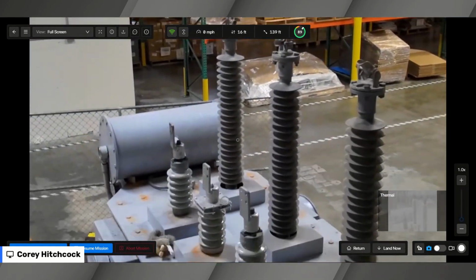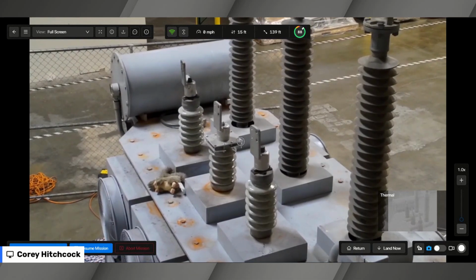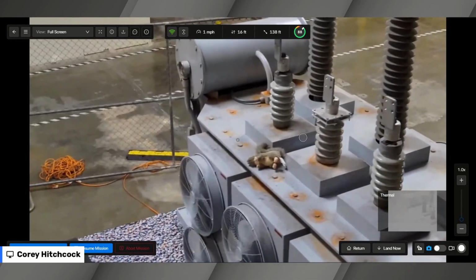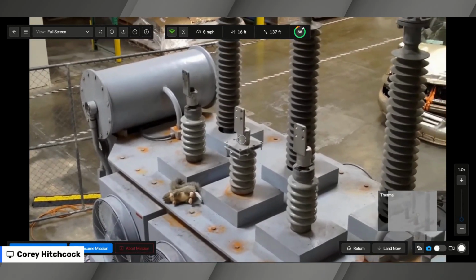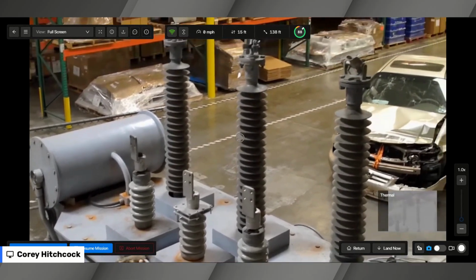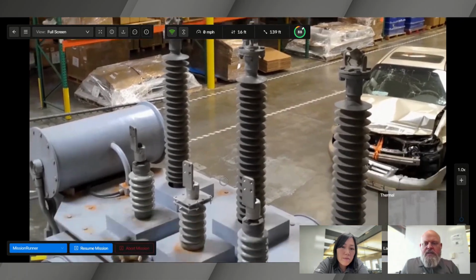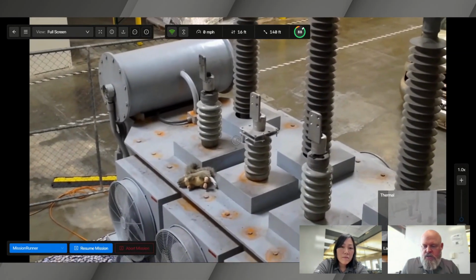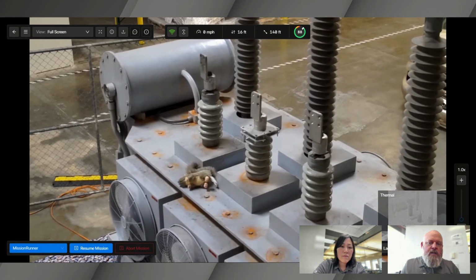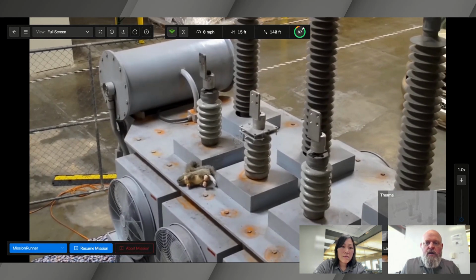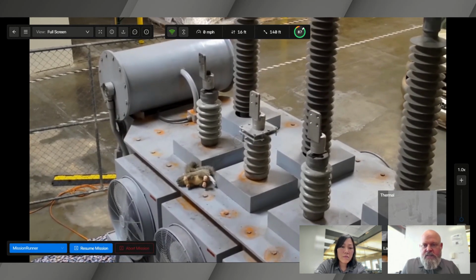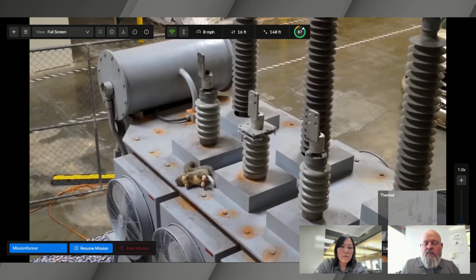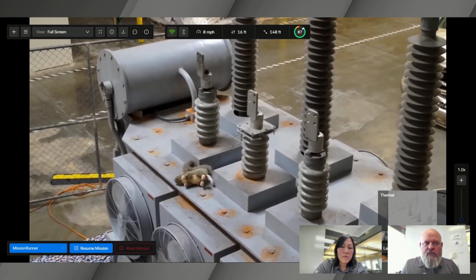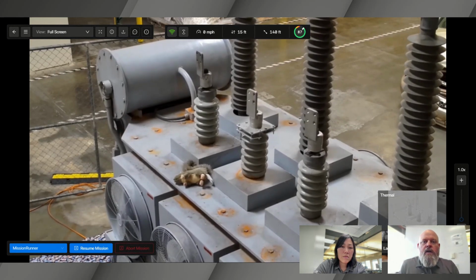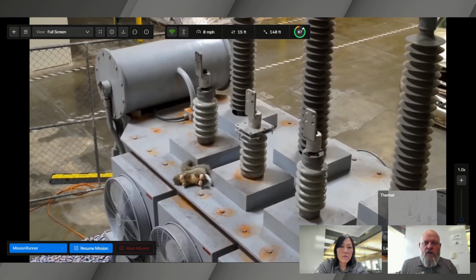Sure, yeah. So something to think about here: we've got our wildlife here that may have caused a differential on this bank, and we know that the bushings seem to be intact, they seem to be okay. So now we can make a decision that we've got this differential on the bank. We can send a test engineer out there to do the atmospherics on the transformer to make sure that it's safe to re-energize. But had we been out here flying and we see the wildlife, or we see a completely blown up bushing, then we know we need a crew, and we can go ahead and start calling that substation maintenance crew and getting them out there.